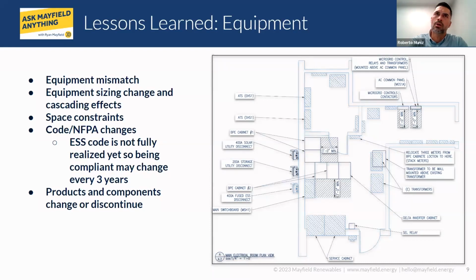The combination of the requirements from the batteries and inverters that are based on the common mode voltage requires that isolation transformer to protect both equipment, the batteries and the inverters. So that isolation transformer helps filter those noises, harmonics, and basically the common mode that the batteries cannot withstand because of all the switching that is happening on the load side of the transformer.